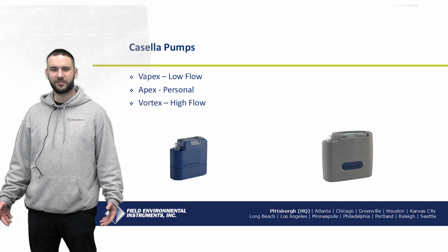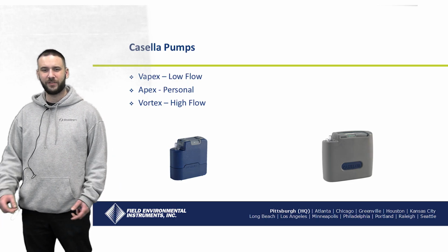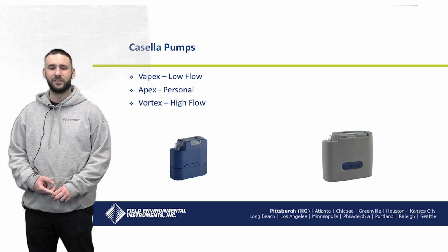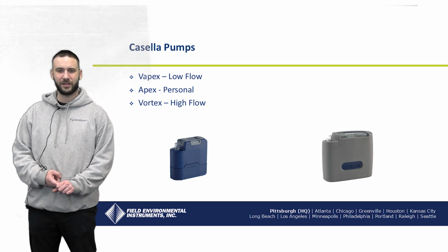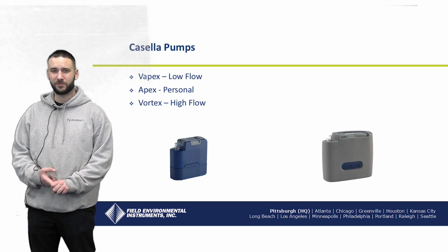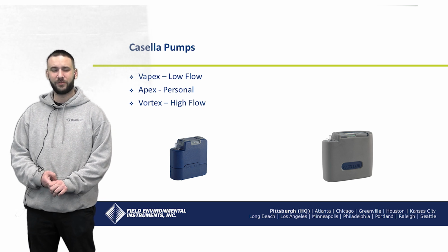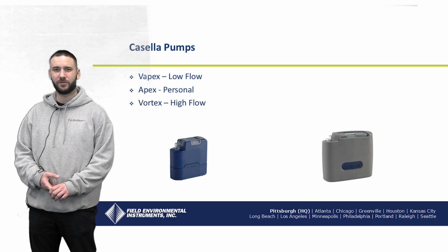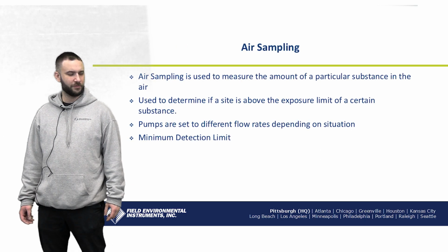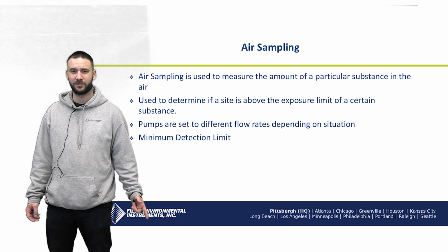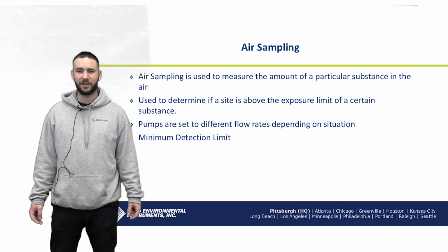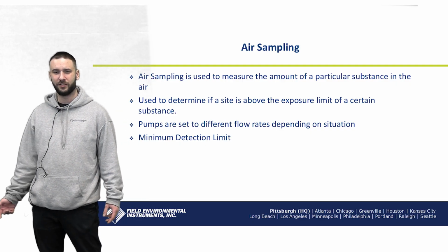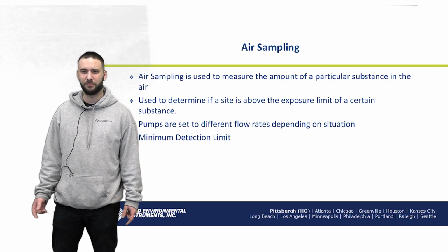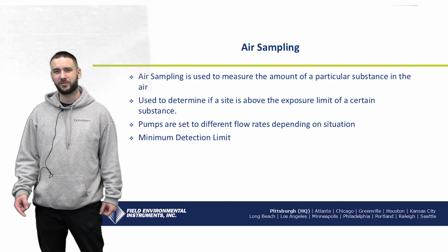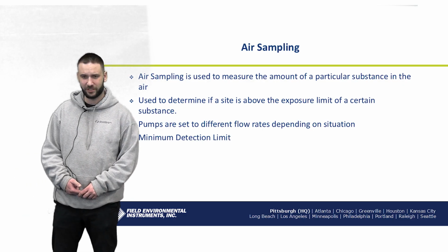If you're not familiar with Casella's air sampling pumps, they have the Vapex, which is their low-flow pump, the Apex, which is their personal medium flow air sampling pump, and the Vortex, which I'm covering today, which is their high flow air sampling pump, which goes between 5 and 12 liters per minute. Now, everything with these pumps has to do with air sampling. Air sampling is used to measure the amount of a particular substance in the air. It's used to determine if a site is above the exposure limit of a certain substance for livability and breathability.